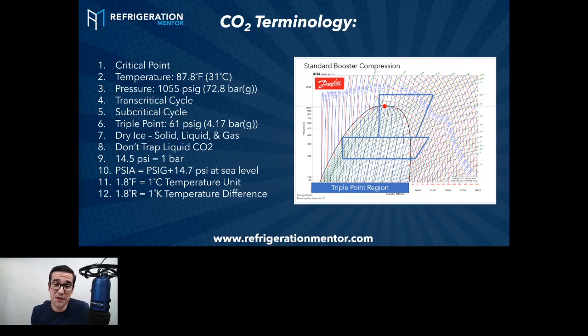Okay. And I know some of you are like, wow, that's 1,055 psi. That's a lot. But think about the transition, for the older guys that were working on R22, where the suction was 65 psi and discharge 275. And then you go to 410A systems, and all of a sudden you're running at 120 suction and 420 discharge. Now, when you look at CO2, they're going to have higher numbers like that. So maybe double what the 410A was, maybe even higher than that, maybe even triple at some points, depending on the design of the system.